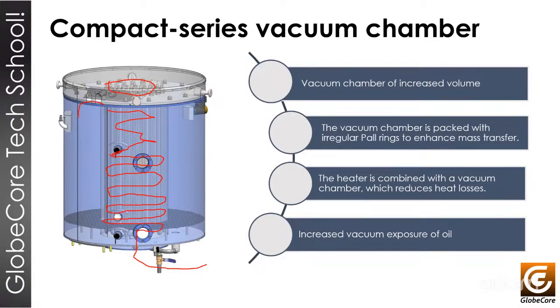This external tank is the vacuum chamber, and it helps us avoid contact of the heater tank with the environment. That means the electrical efficiency of this machine is really high, because all the heat generated by the electricity in the resistors is transferred directly to the oil, and the vacuum chamber acts like a special barrier that avoids contact of the heat of the resistors with the environment. That helps the electrical efficiency of the machine in a really big way, and it makes the heat transmission really good for this kind of machine.